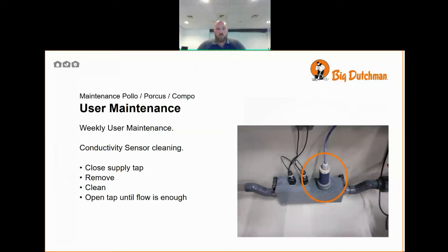Also on the user weekly maintenance, we need to clean the conductivity sensor. In the same way, we close the tap and remove the sensor, clean it with a soft clean rag, making sure that the eye through the sensor is clear, and then reinstall, making sure that the stainless steel pin is into the flow that is coming into the sensor block, and then open the tap until the flow is correct.